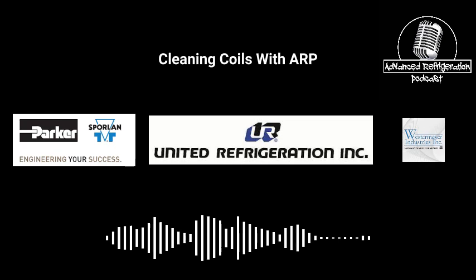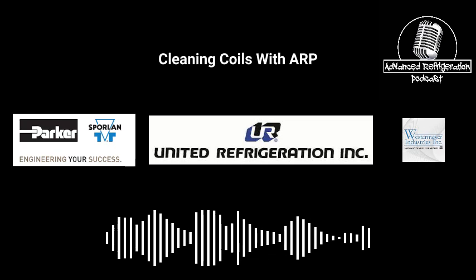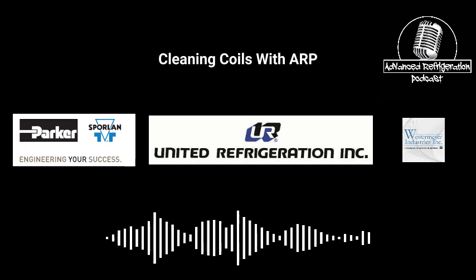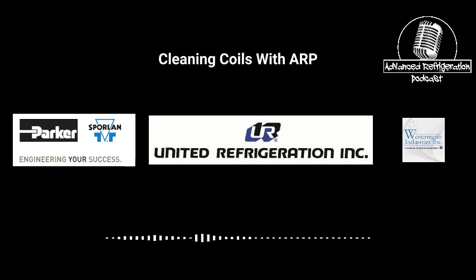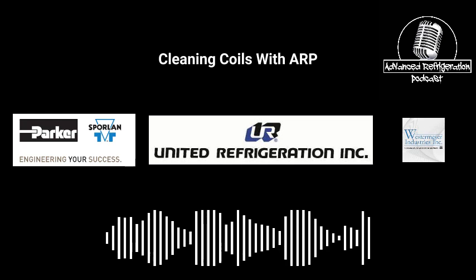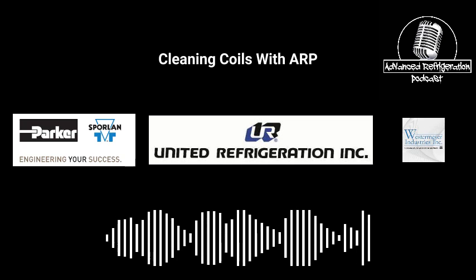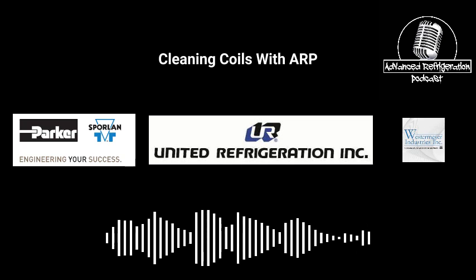You want to use a real wide tip. You don't want to fan back and forth and bend the fins. You want to use a real wide tip so that you can push that water down in there. And if you guys have access to it, a Hotsy, amazing. We use a Hotsy a lot, so we don't use a lot of chemicals. That heat does more for it than chemicals do at some points.